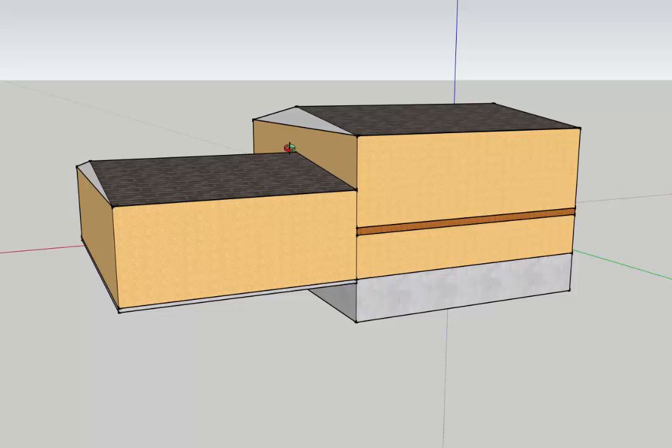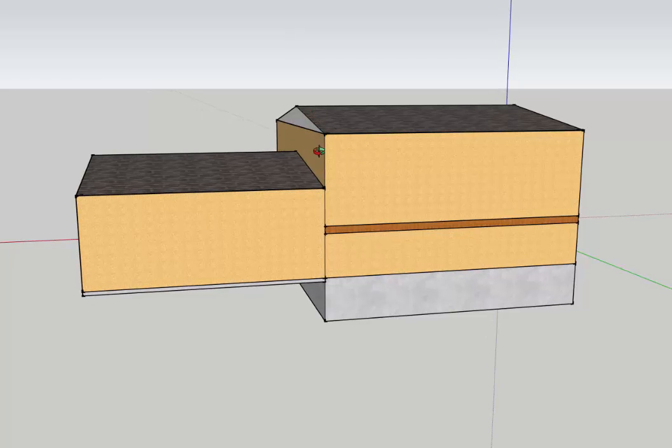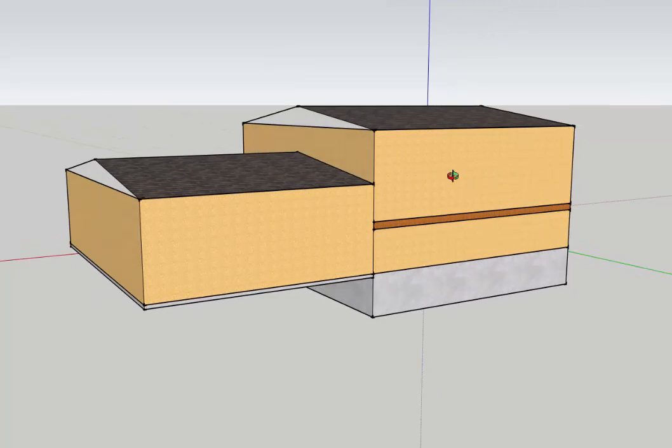or if you want to make sure that you get that buffered space out of there, you could do that as well. Either way, you want your insulation to go down until it hits whatever that level of insulation is in this attic, so that you complete your thermal boundary here. But either way, you want to make sure that you're representing each of these surface areas in the audit so that the audit can evaluate the total heating and cooling loads or heat losses of this house.